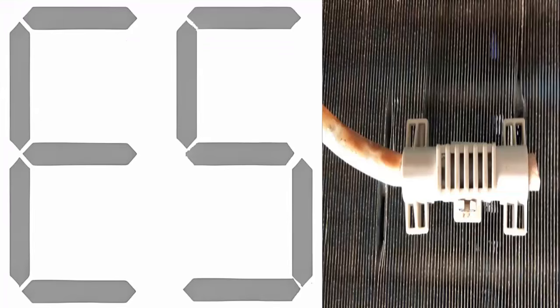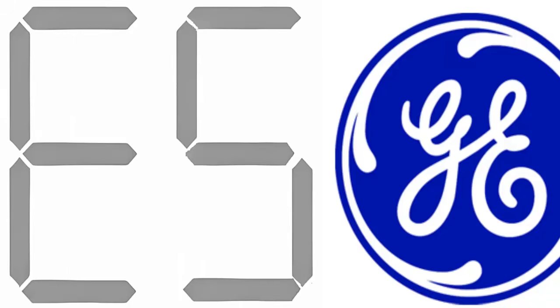Some of the most famous brands that associate the E5 error with the temperature sensor are: A. General Electric. The E5 error reflects an open circuit or short circuit of the external temperature sensor. For the portable air conditioner from this manufacturer, error code 5 means the presence of an overcurrent protection for the equipment.